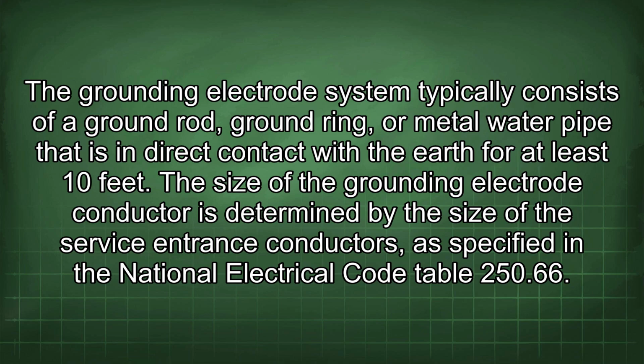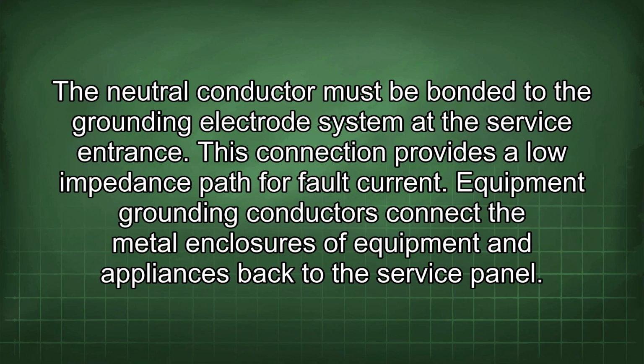The size of the grounding electrode conductor is determined by the size of the service entrance conductors, as specified in the National Electrical Code Table 250.66. The neutral conductor must be bonded to the grounding electrode system at the service entrance. This connection provides a low impedance path for fault current.